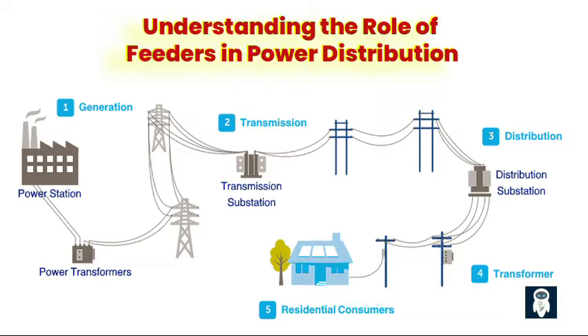Third, for voltage regulation: maintaining stable voltage levels is crucial for reliable operation of electrical devices. Feeders employ voltage regulation techniques to compensate for voltage drop that occurs due to the resistance and impedance of the distribution lines. Voltage regulators and capacitors are often used along the feeder to regulate and stabilize the voltage within acceptable limits.